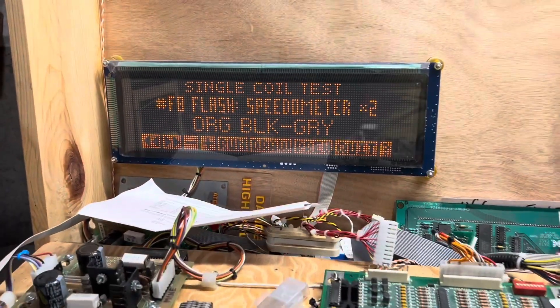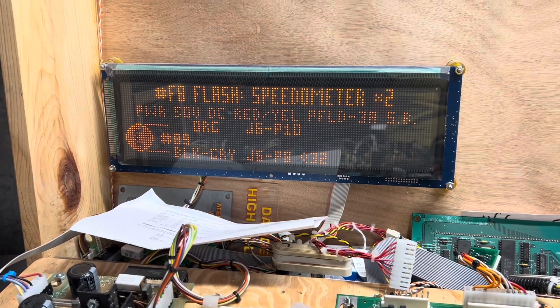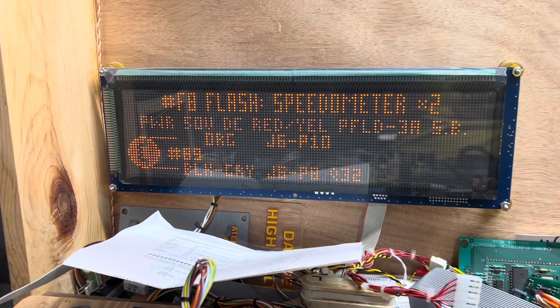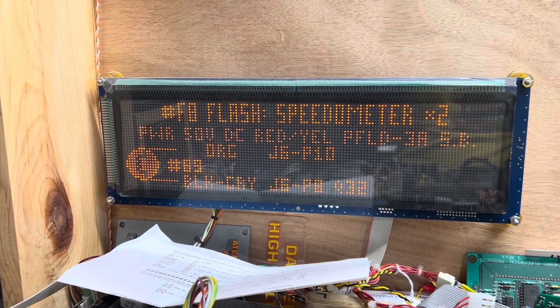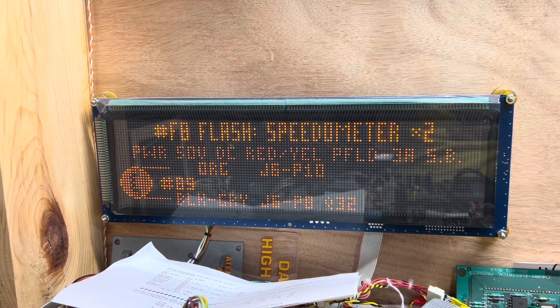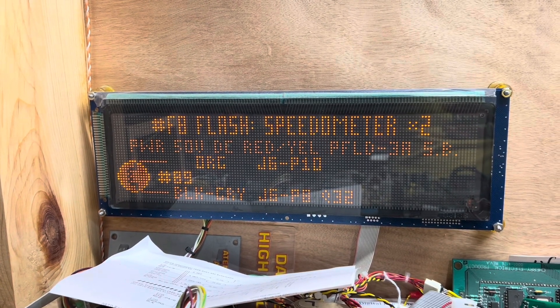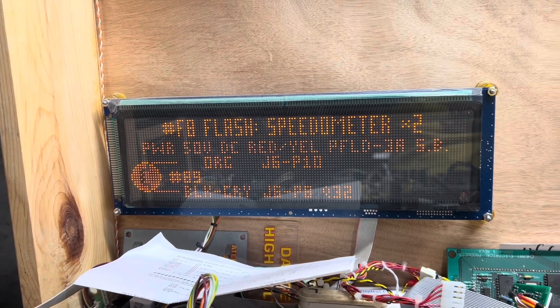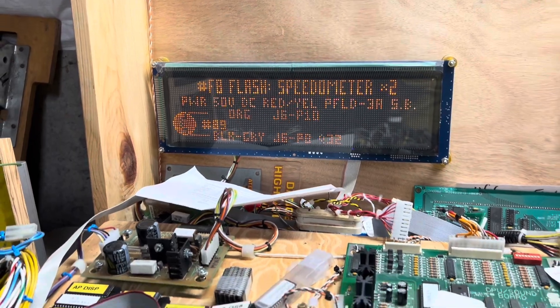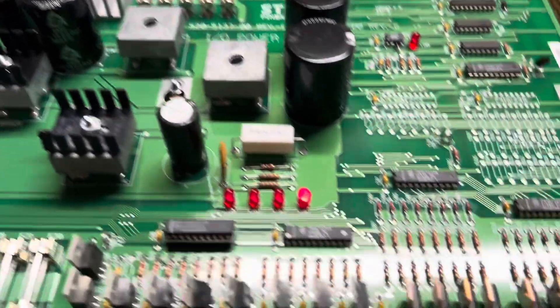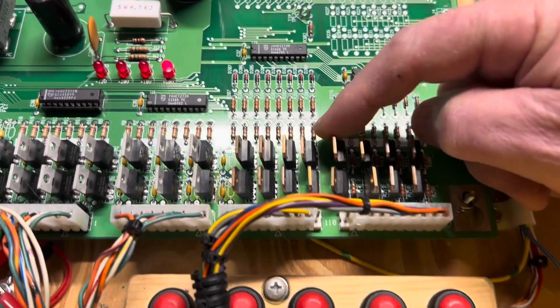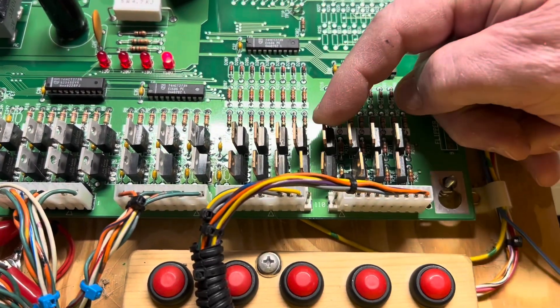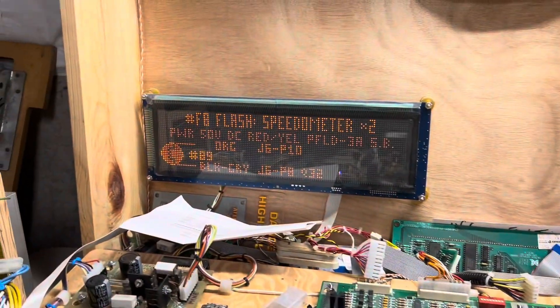So here's one of the cool things about White Stars. You can draw the circuit. And this is going to tell me that it drives a number 89 flash lamp. And the orange wire, J6P10, provides the power to the flash lamp. And the black-gray wire, J6P8, which is driven by Q32, is where it finds a path to ground. Now, Q32 is this one. It's not one that I replaced. That is a TIP 122. So I'll get my meter out and diode test that.